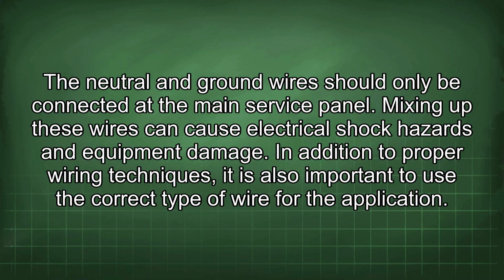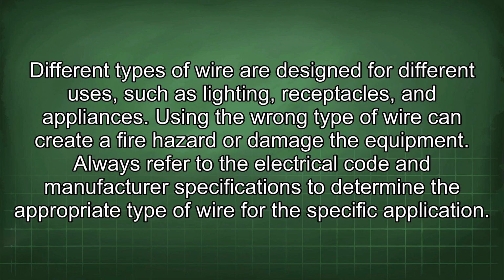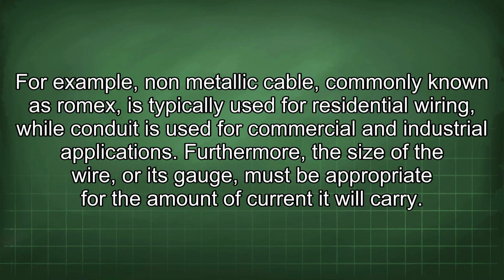In addition to proper wiring techniques, it is also important to use the correct type of wire for the application. Different types of wire are designed for different uses, such as lighting, receptacles, and appliances. Using the wrong type of wire can create a fire hazard or damage the equipment. Always refer to the electrical code and manufacturer specifications to determine the appropriate type of wire for the specific application. For example, non-metallic cable, commonly known as Romex, is typically used for residential wiring, while conduit is used for commercial and industrial applications.